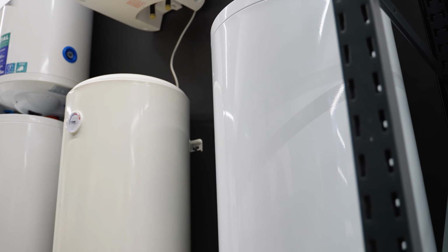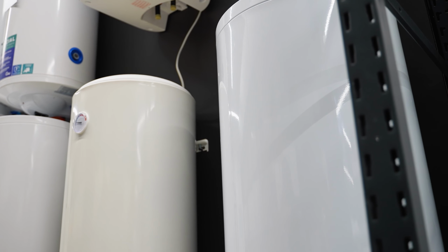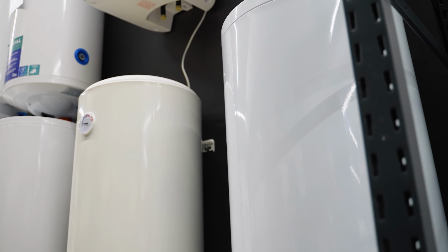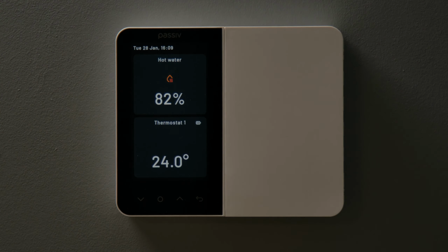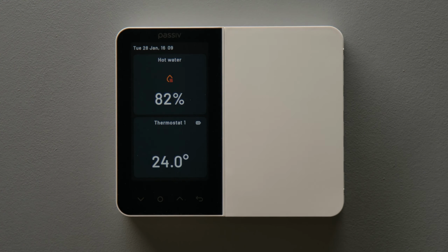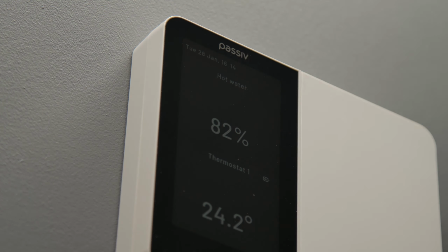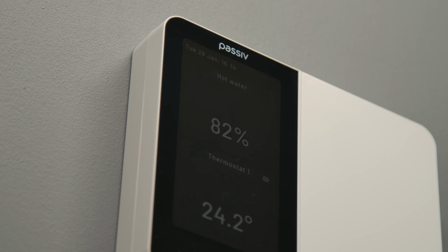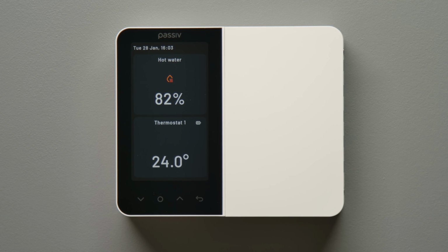In this video, we will cover how to test that the immersion element of the hot water tank is functioning correctly. You can test the immersion element using the Passiv programmer. Note that testing the immersion can take over an hour, as the Passiv Smart Thermostat will utilize the heat pump initially to reduce electricity usage.